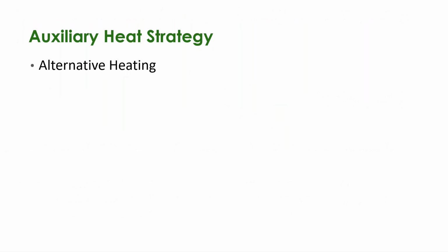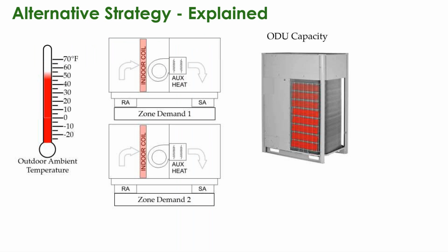Probably the more commonly used auxiliary heat strategy is something we call alternative heating. This comes into play much more in extremely cold climates or areas where we want to have some extra safety. As the outdoor temperature drops, the outdoor capacity reduces, and at a given point, based off of fuel costs, electric costs, as the COP of that outdoor unit is dropping, it may become more beneficial to switch the heat source altogether over to something else.